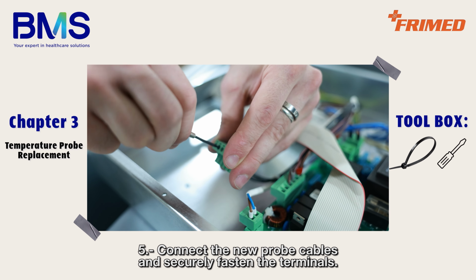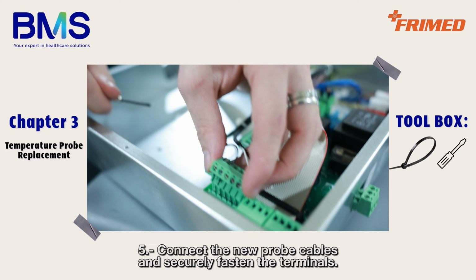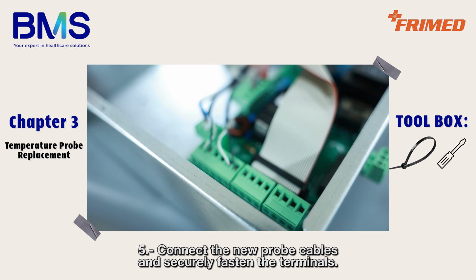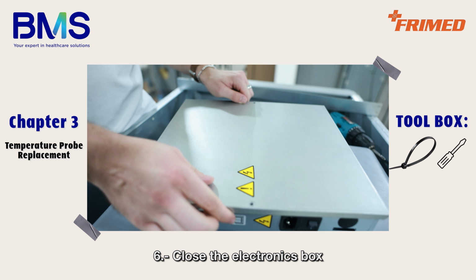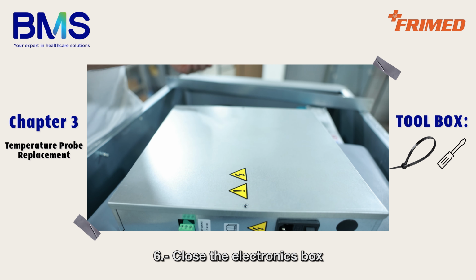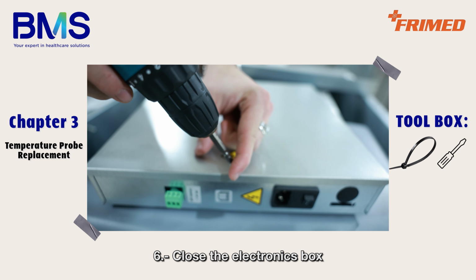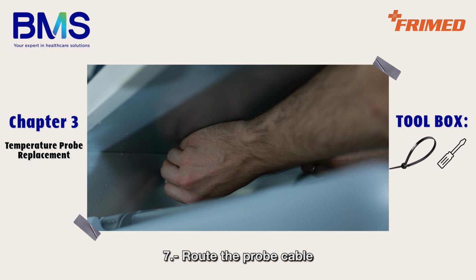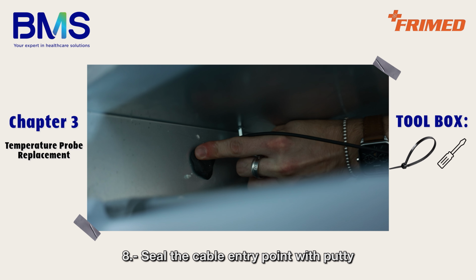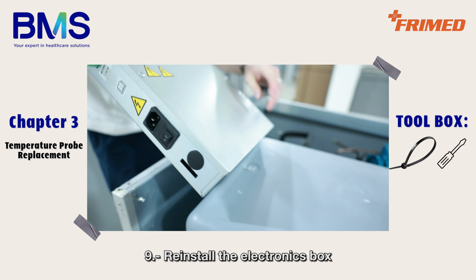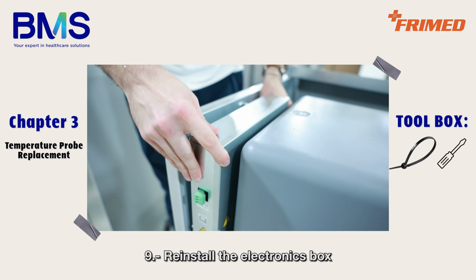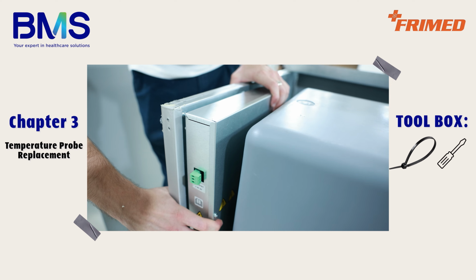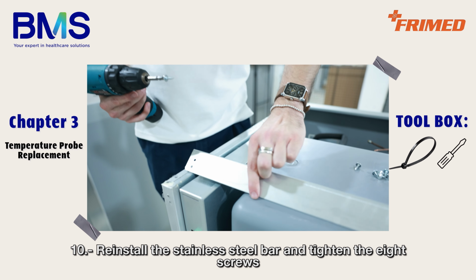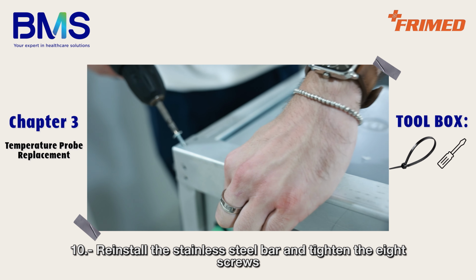Connect the new probe cables and securely fasten the terminals. Close the electronics box. Route the probe cable through the designated opening and secure it as previously described. Seal the cable entry point with putty and reinstall the electronics box in its original position. Reinstall the stainless steel bar and tighten the 8 screws.